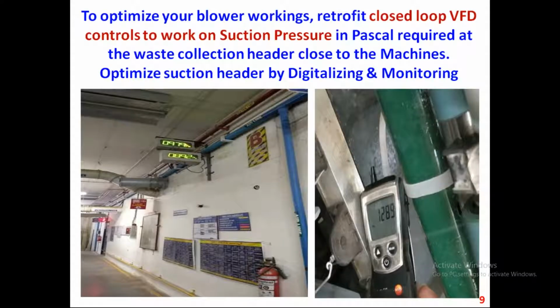This is in a textile mill waste collection system. They are able to see on the header what it is: almost 1000 pascal. And the pressure required at the machine end is only 600 pascal. So how much can be saved? Digital in situ measurement can be fixed, like this type of header monitoring, or it can be a portable kit. Testo or other branded portable meters are available. It can measure in pascal, and you can see what pascal you are monitoring at this fan.